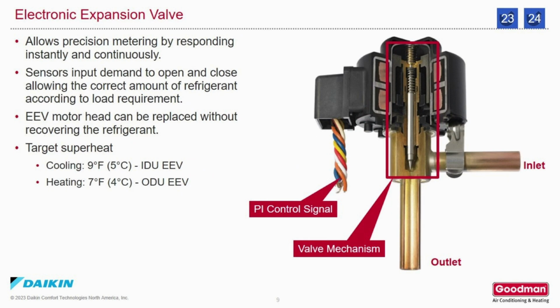The electronic expansion valve allows precision metering by responding instantly and continuously. It also has the ability to meter in both directions. Sensors input demand to open and close, allowing the correct amount of refrigerant according to the load requirements. The EEV motor or power head can be replaced without recovering the refrigerant. Your target superheat in cooling is 9 degrees Fahrenheit on the indoor unit EEV, and in heating is 7 degrees Fahrenheit on the outdoor unit EEV.